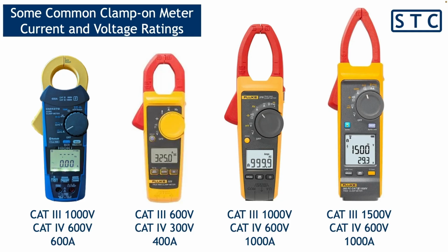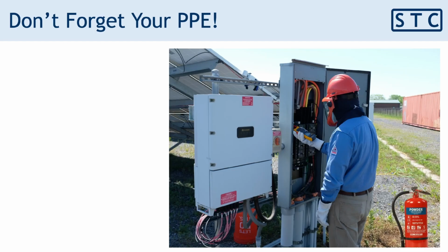Let's look at some common clamp-on meter current and voltage ratings. These will always be marked on the case of the meter itself. It's going to vary exactly where, but if you look, you'll find them. You can see that there's quite a bit of variation for the Cat 3 and Cat 4 voltage ratings, as well as in the maximum amount of current that they can measure. You end up paying for those higher voltage and current ratings. So if you're selecting a meter, you're going to want to choose a meter that's appropriate to the type of work that you're doing. PPE, personal protective equipment, is your last line of defense when things go wrong.